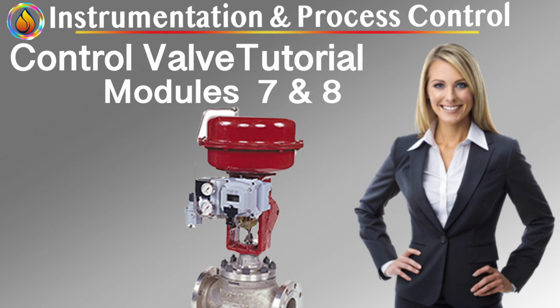Valve performance is not binary. A valve does not simply work or fail. It exists on a continuum between transparent control element and dominant disturbance source. Engineers who understand and quantify this behavior move beyond firefighting and begin designing loops that remain stable, efficient, and predictable throughout the valve's life.